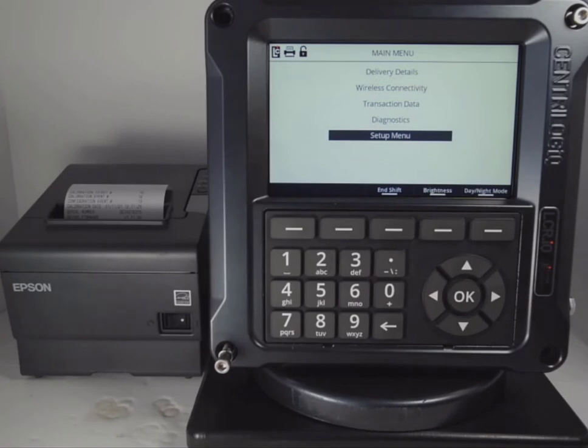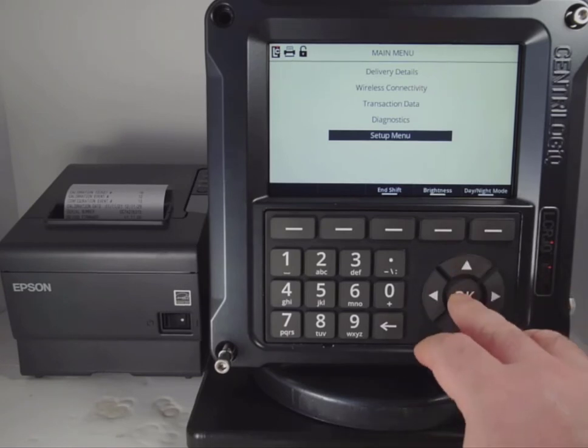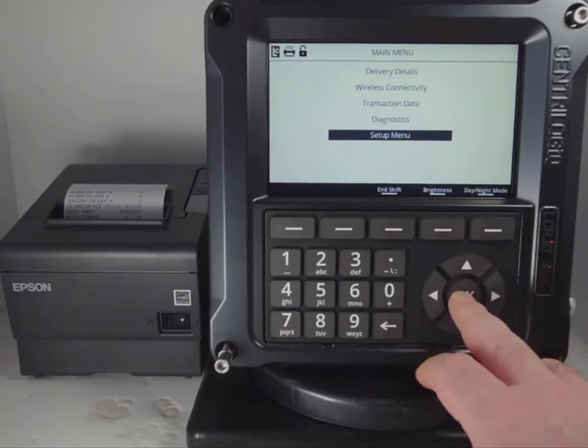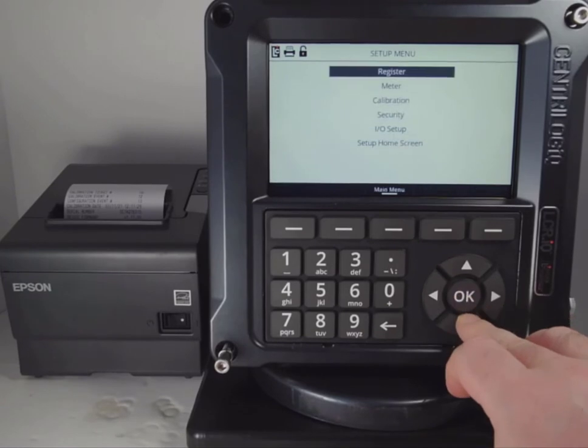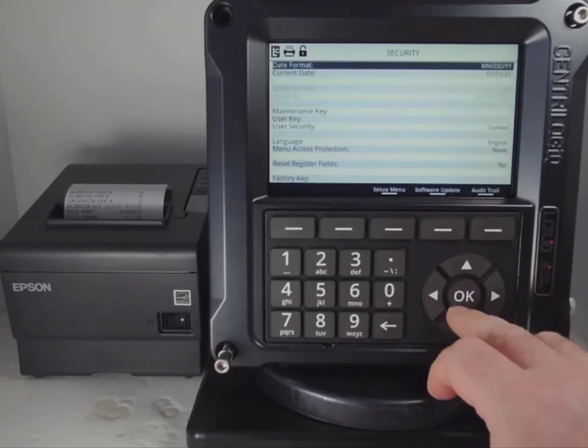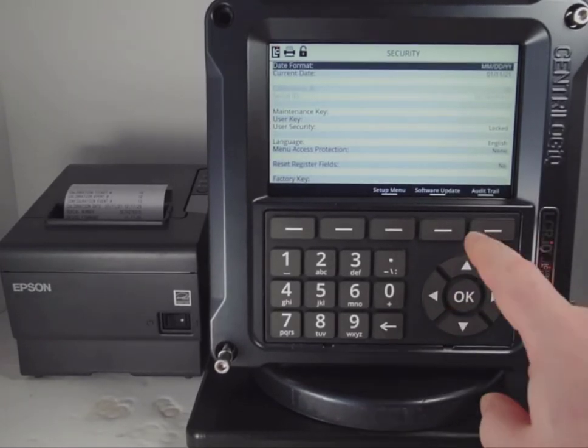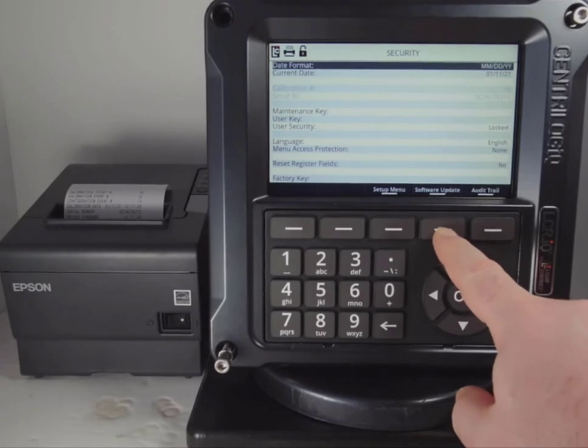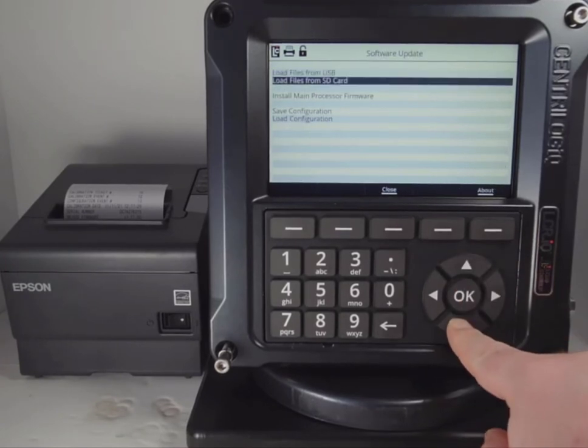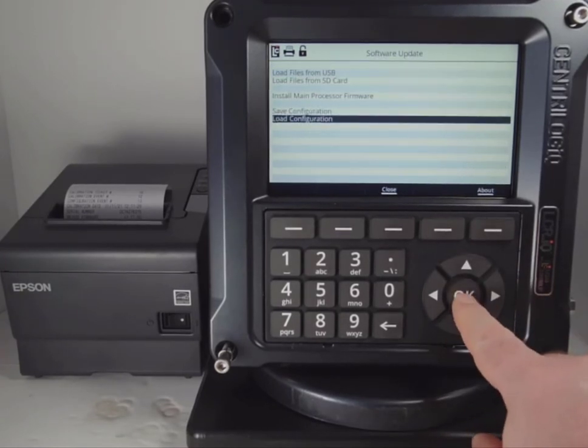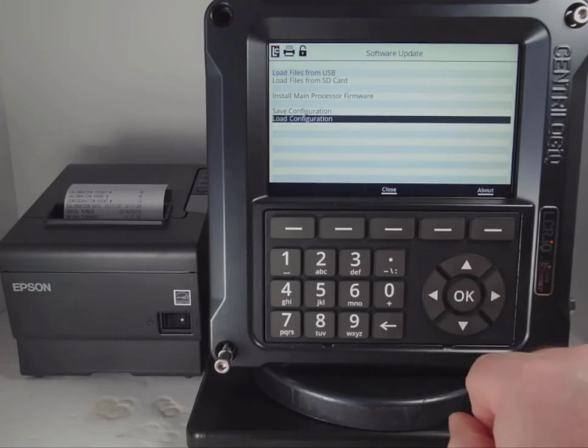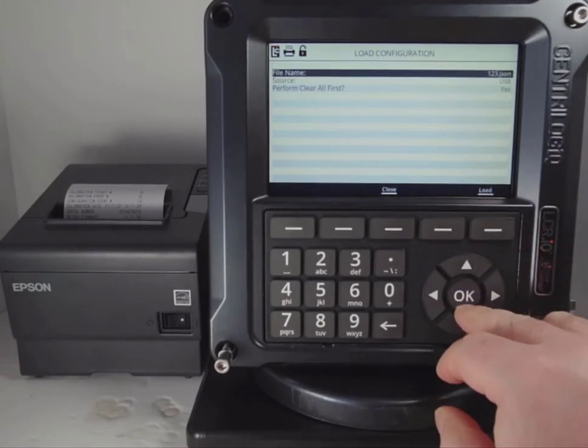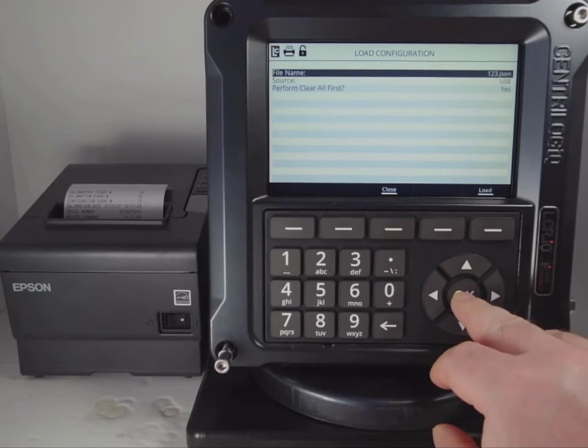Once you've upgraded the software, if you saved your configuration and want to load it back into the register, simply go back into the Update Software section. I'm going to go to the Setup menu, into the Security section, and with the switch still in the calibration position, press the Software Update button, then go to Load Configuration and press OK. That will load any of the configurations I have saved into my register.